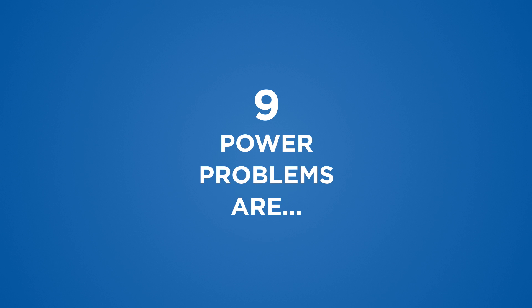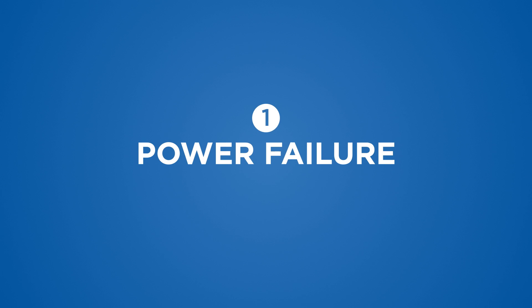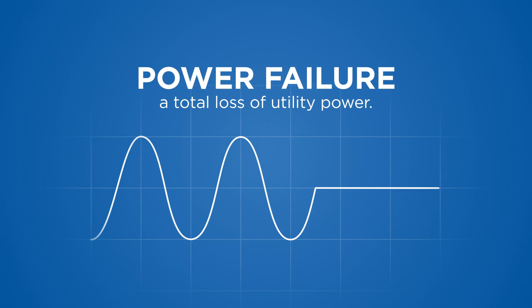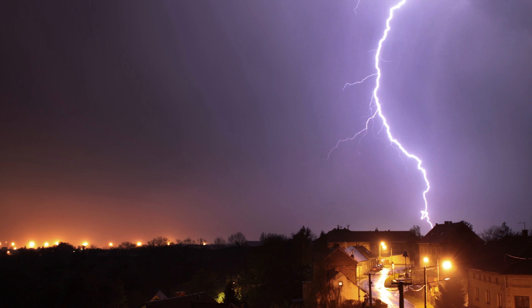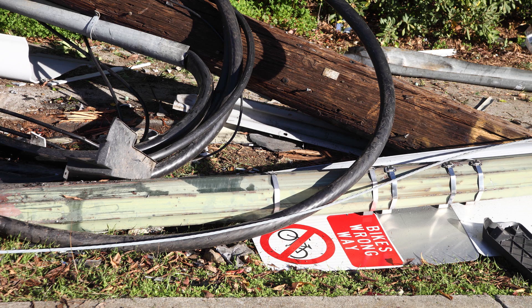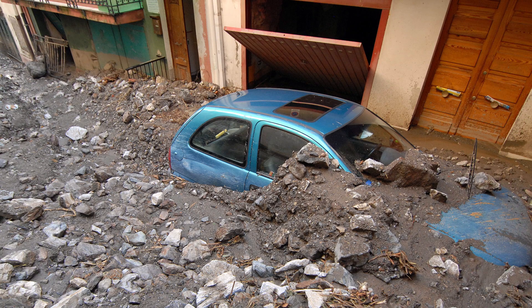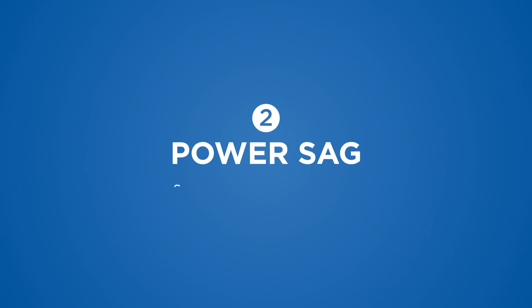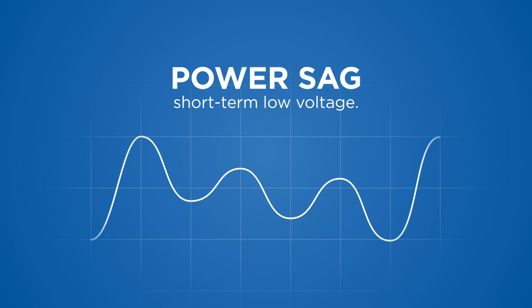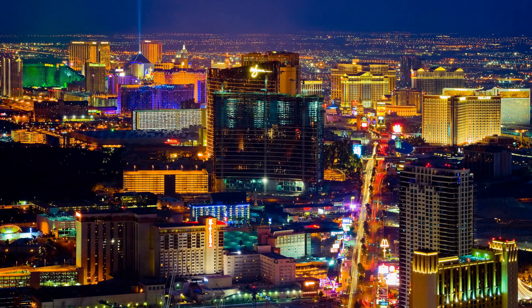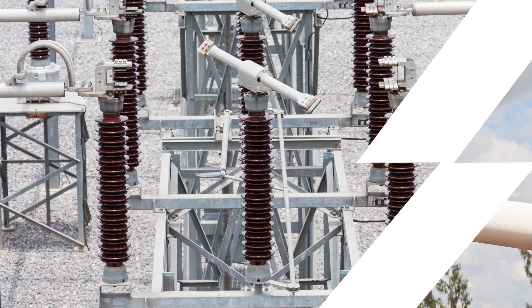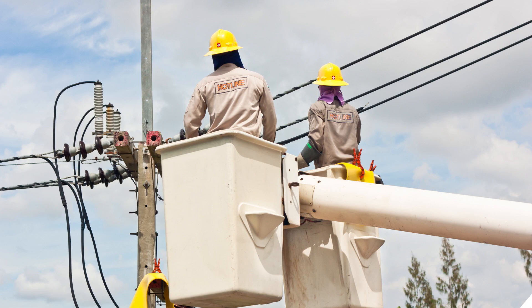The nine power problems are as follows. Power failure: a total loss of utility power. This can be caused by lightning strikes, downed power lines, grid over-demands, accidents, and natural disasters. Power sag: short-term low voltage, triggered by the startup of large loads, utility switching, utility equipment failure, lightning, and power service that's too small for the demand.